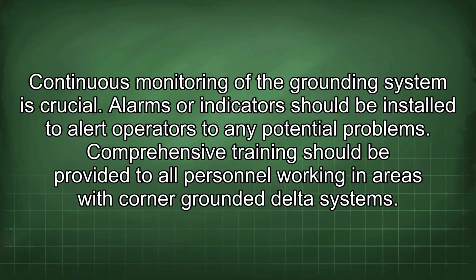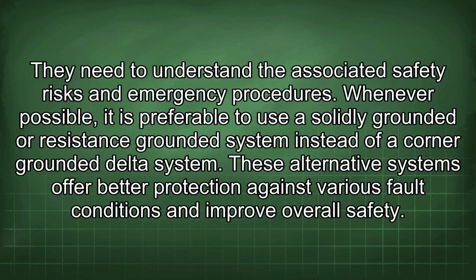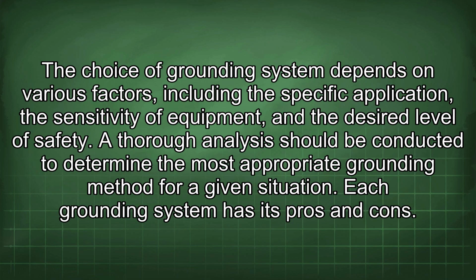Comprehensive training should be provided to all personnel working in areas with corner-grounded delta systems. They need to understand the associated safety risks and emergency procedures. Whenever possible, it is preferable to use a solidly grounded or resistance-grounded system instead of a corner-grounded delta system. These alternative systems offer better protection against various fault conditions and improve overall safety. The choice of grounding system depends on various factors, including the specific application, the sensitivity of equipment, and a desired level of safety. A thorough analysis should be conducted to determine the most appropriate grounding method for a given situation.